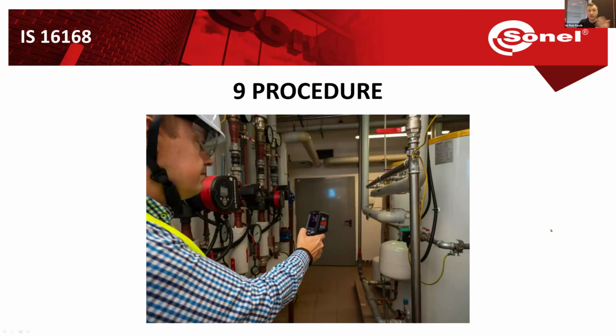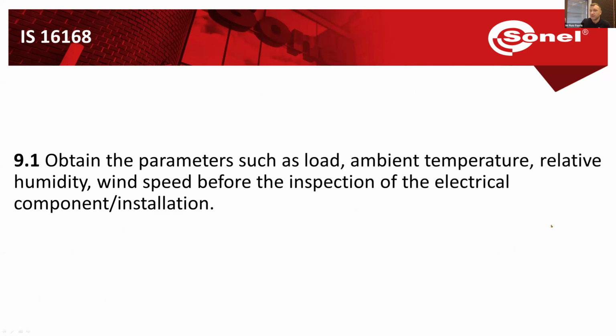Okay, now let's look at the procedure of taking a picture. First, we need to check parameters such as the load of our installation. Remember, we need to make thermal imaging studies typically on live energized installations. Why is that? If the installation is de-energized, there's no load, so there will be no overheating effect, no heating effect, and we would not be able to spot any abnormalities.